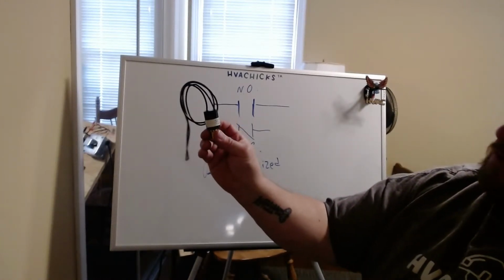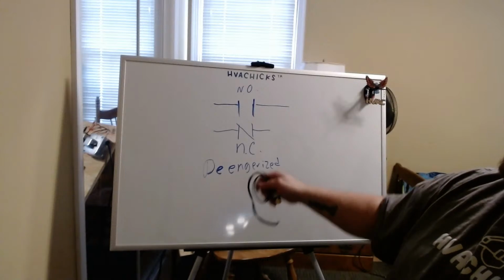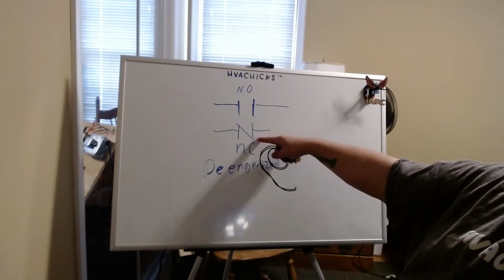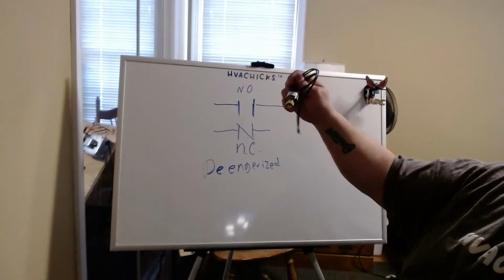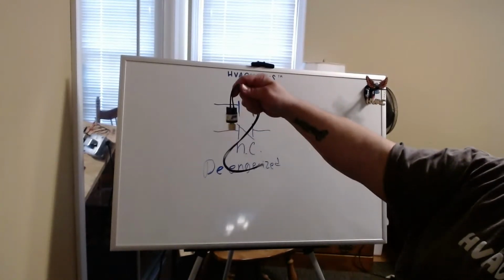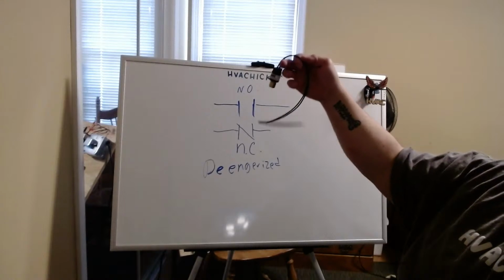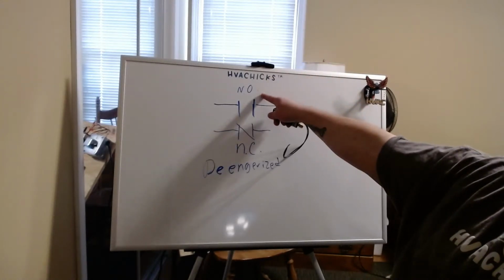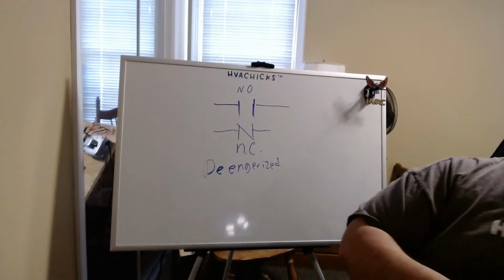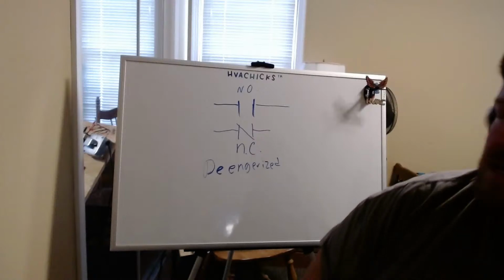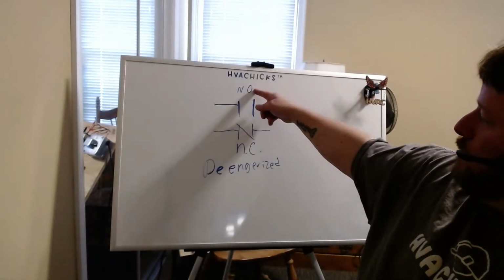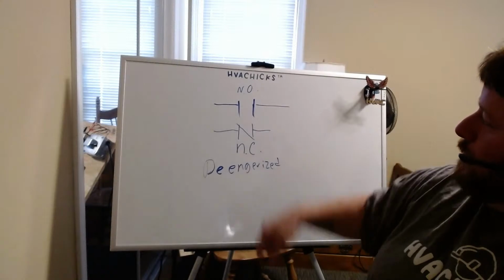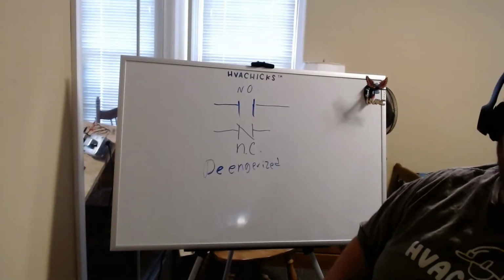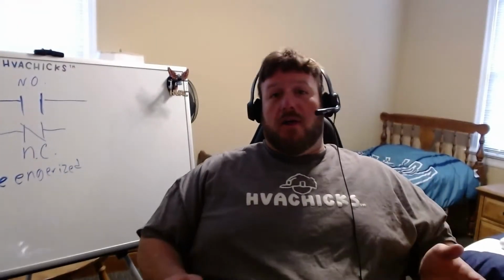Your high pressure switch is shown normally closed because there's no pressure to open the switch. Your low pressure switch, because there's no pressure to close it, is shown normally open. Your fan relays, depending on the style, depends on how it's shown, should be shown normally open on one of the two terminals. Everything is shown as de-energized. All your relays and controls are done like that.